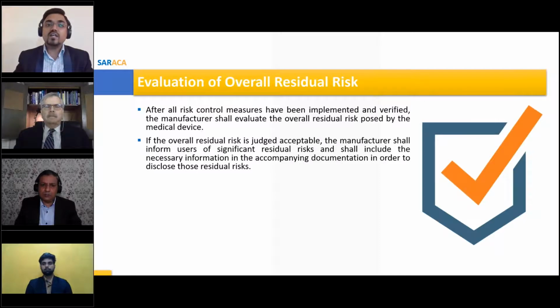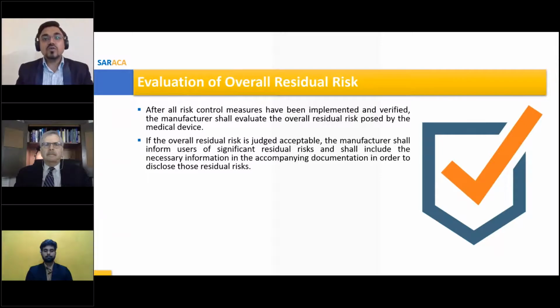Then you find there are still risks associated with your medical device. Those are called overall residual risks. Here you can evaluate those overall residual risks, and you need to overlay and check the criteria. Then you need to check whether these overall residual risks are acceptable or not acceptable. This acceptability of the overall residual risks has already been defined in your RMP, the risk management plan.